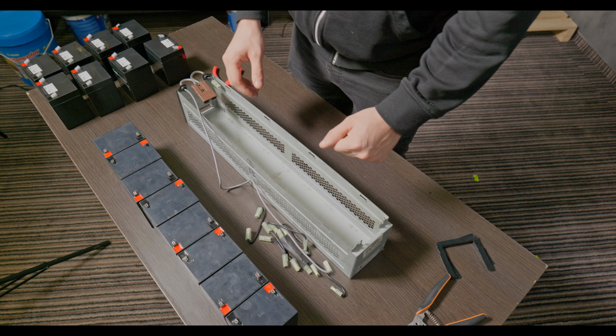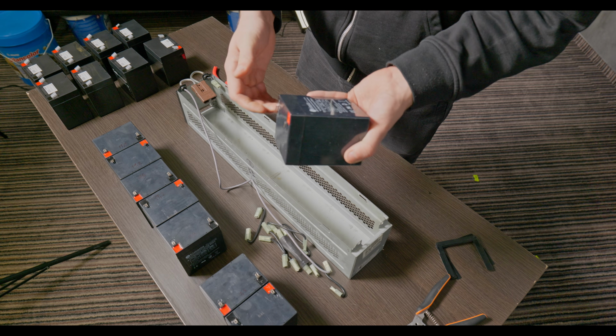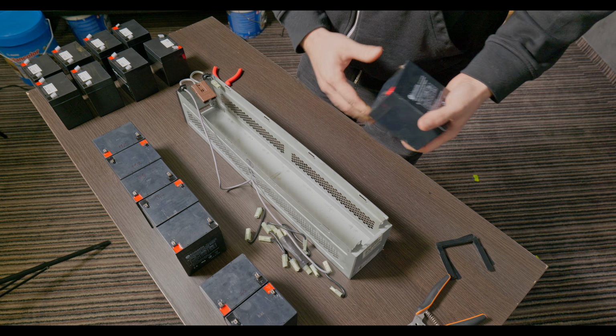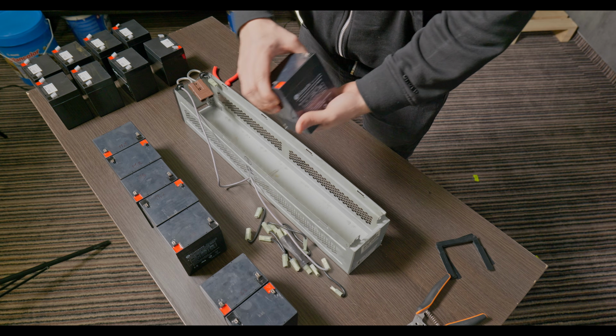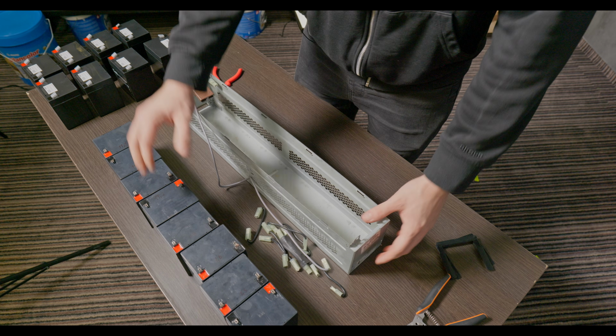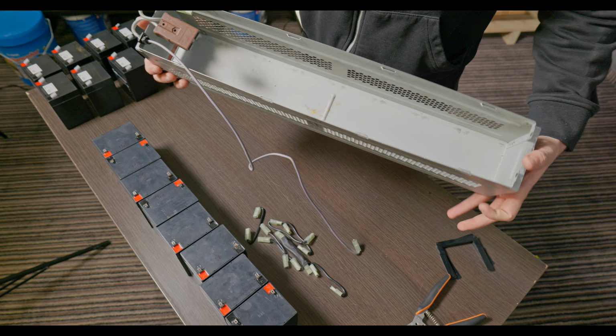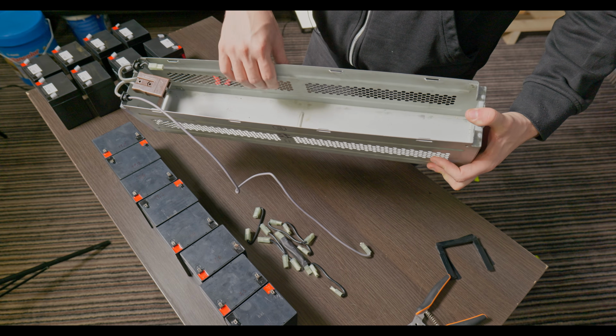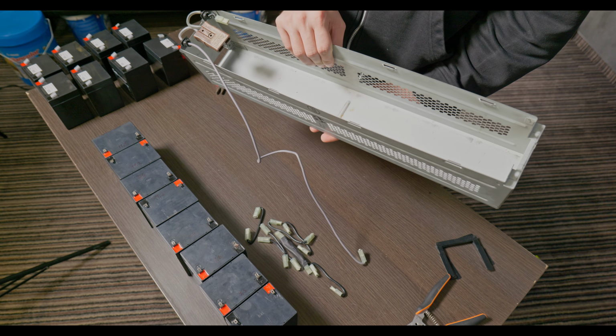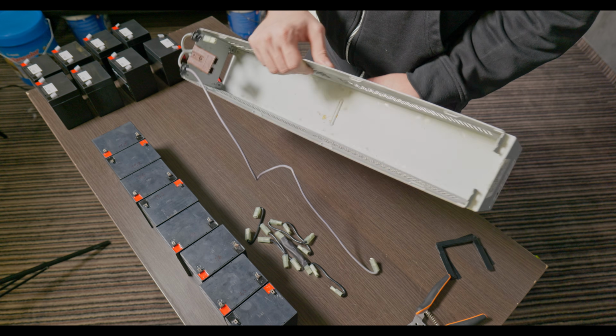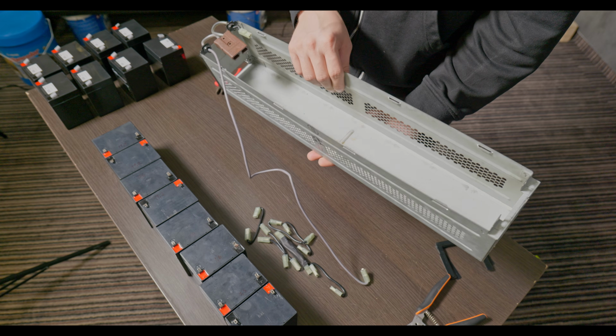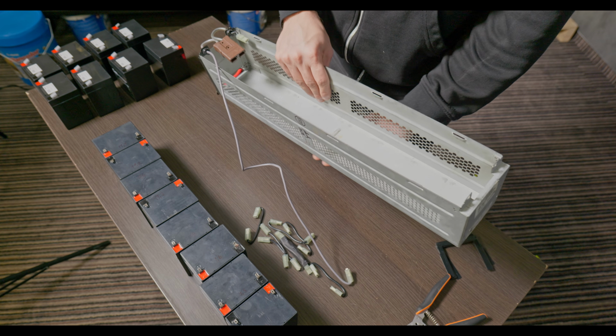So the batteries are out. You can look at the batteries to see if they are leaking or something, and you need to clean up this shelf, because sometimes it will have rust on the bottom. If the rust is severe, you need to change this shelf. It's like 150 euros, I know, but you should change it.